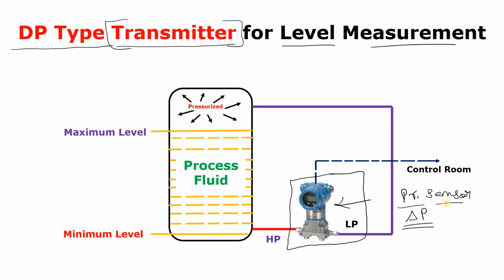That pressure sensor will convert the measured pressure, which it measures because there is an HP tapping and an LP tapping, into other parameters. The parameters may be millivolts, capacitance, resistance, etc. It depends on the type of pressure sensor we are using inside the DP type transmitter. Generally, what I have seen in the industry, and you will also see, is that we use the Wheatstone bridge.